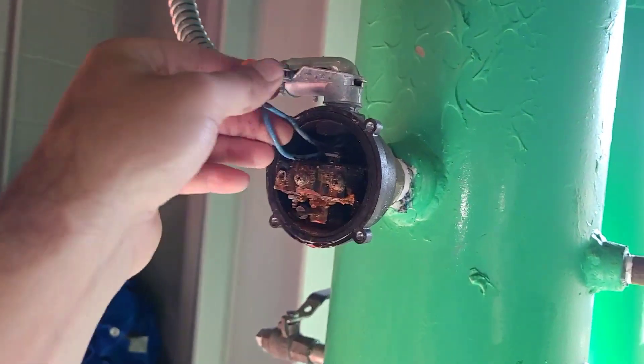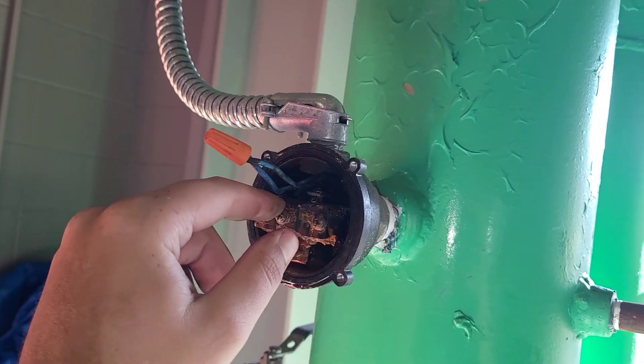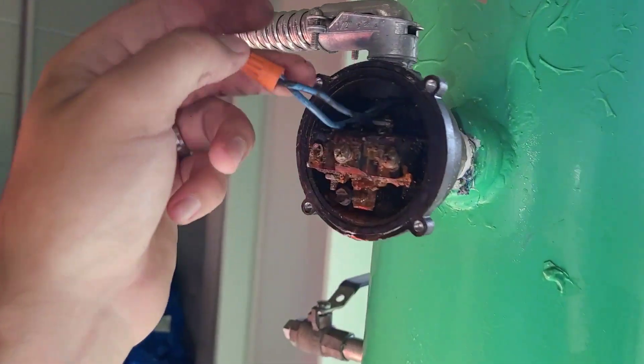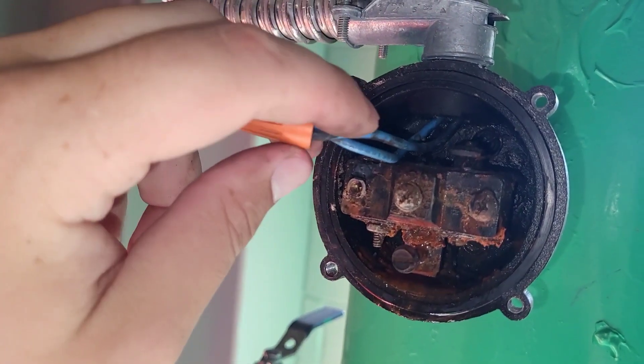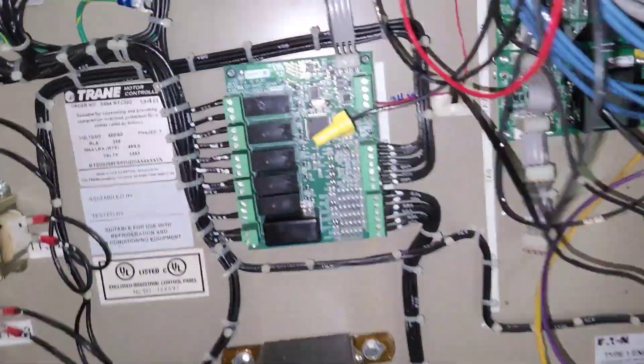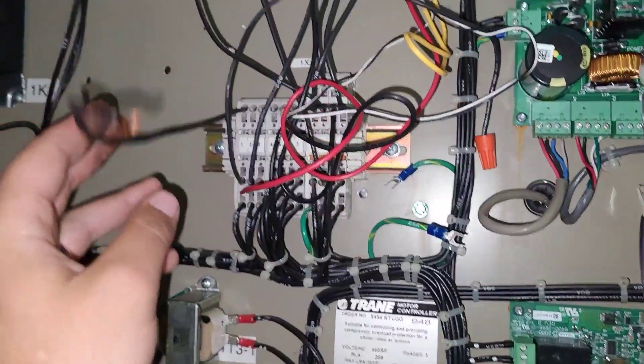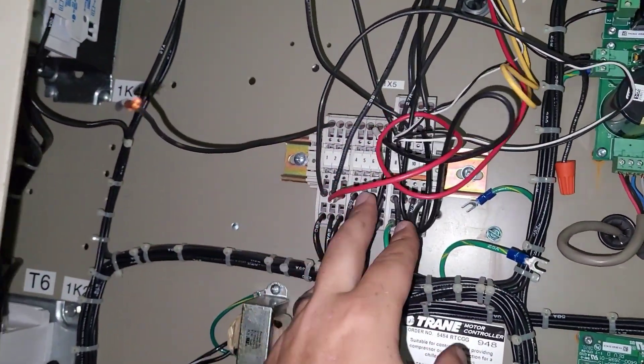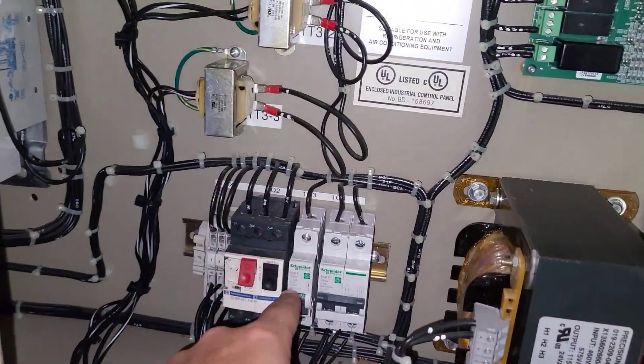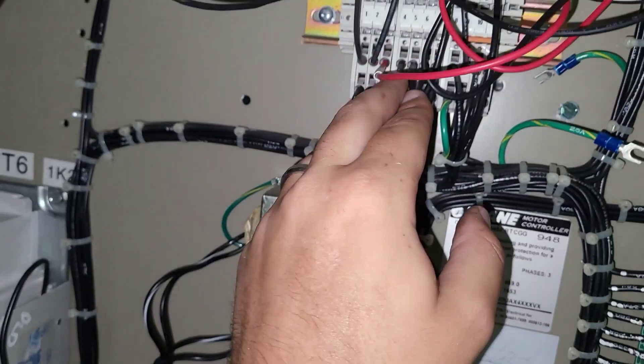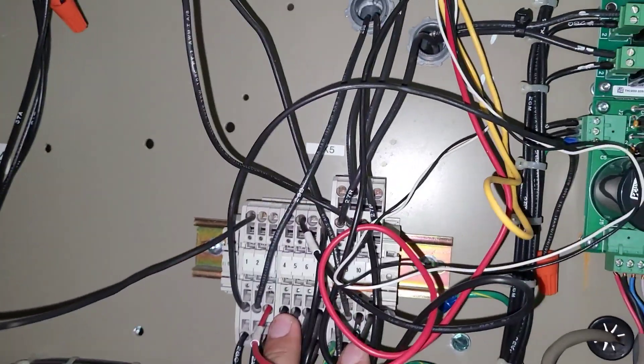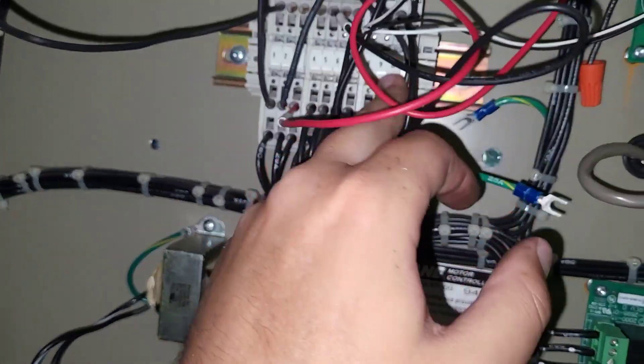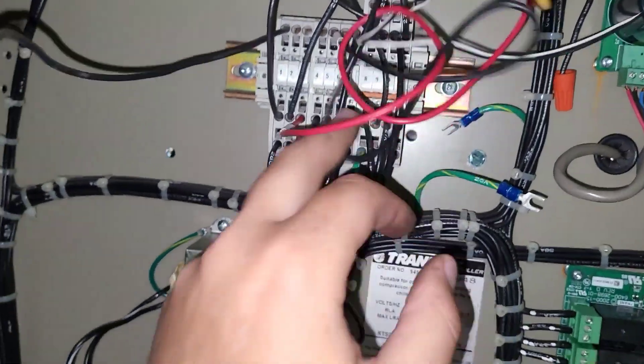What we're going to do as a temporary—this switch is just shorting internally. Actually, I got to looking closer, one of these wires was direct shorting out and actually it burnt. Anyway, that'll take care of our short. Basically, the way this went is your main power legs come in from the transformer, feed through this 120 breaker into this 1x5 terminal block. Terminal 4 and terminal 8 are those connectors.